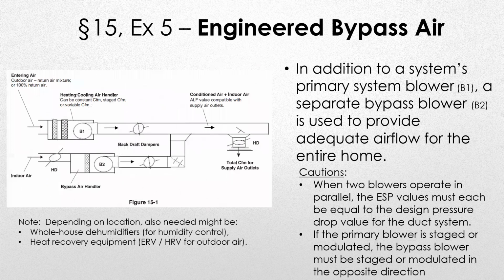Engineered bypass air. This would be a play on a mixing box. The difference is you're paralleling 2 blowers. So you could have, if the first one is 400 CFM for your air handler system and you only needed another 400, you would have a bypass air handler that would bring in outdoor air, or the other one could be. You just have a second air handler that you'd put in parallel and then basically wire them together to the distribution system to do that.